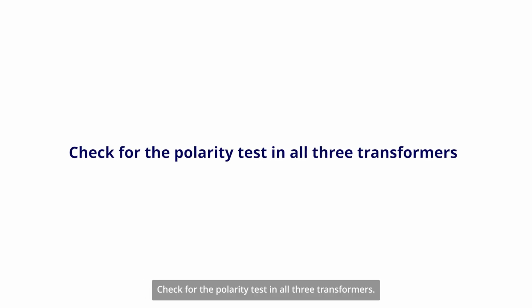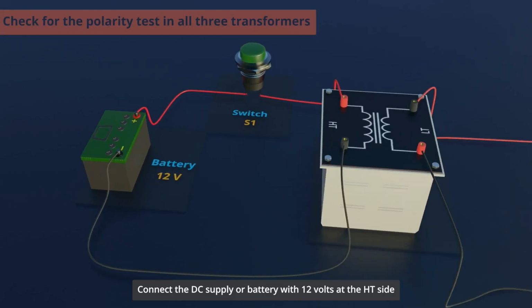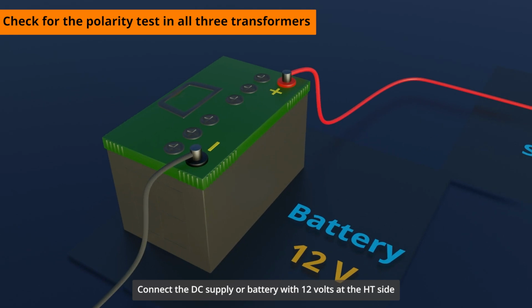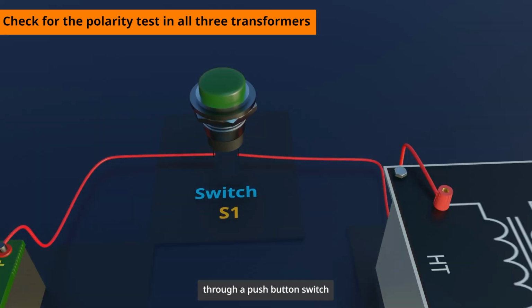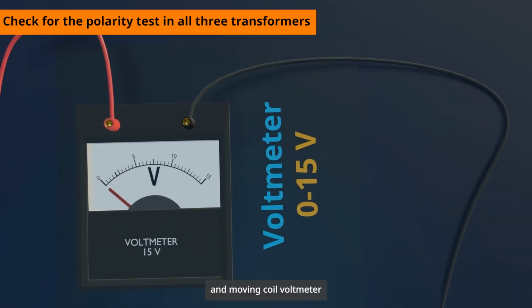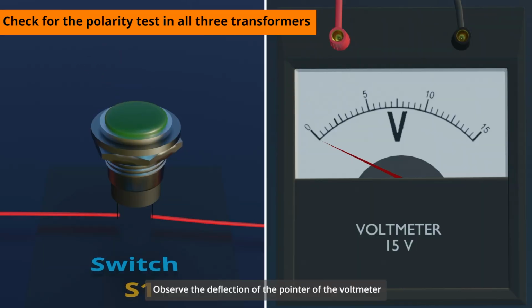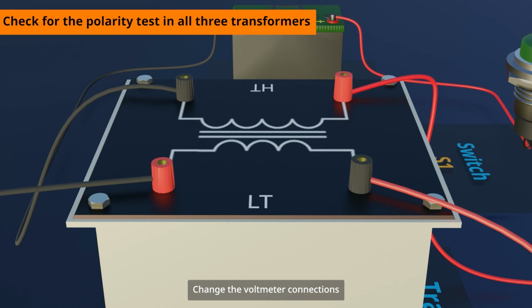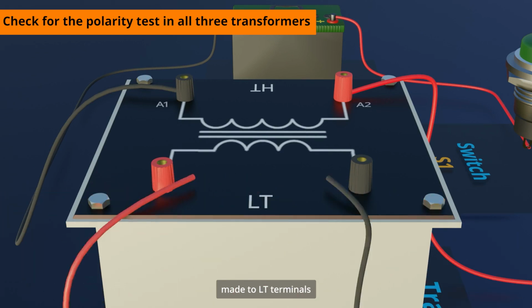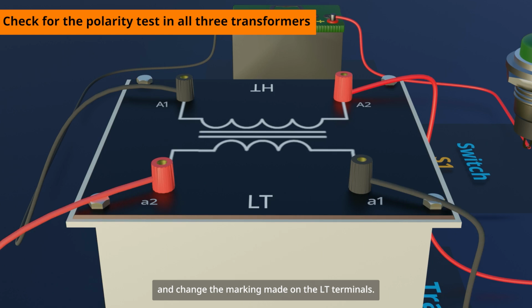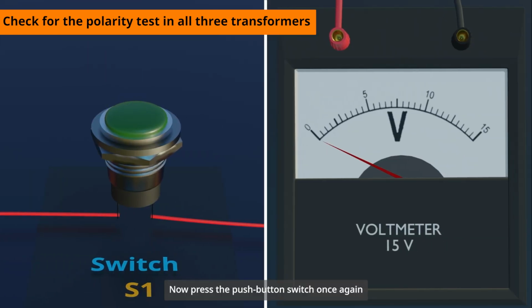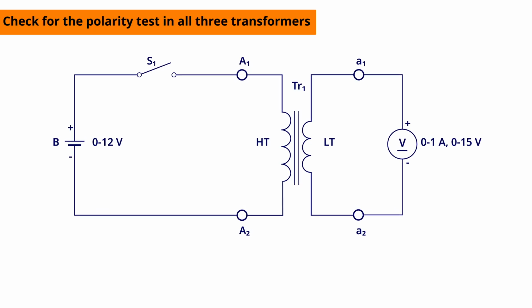Check the polarity test in all three transformers. Connect the DC supply or battery of 12 volts at the HT side through a push-button switch, and a moving coil voltmeter ranging from 0 to 15 volts at the LT side. Press the push-button switch. Observe the deflection of the pointer of the voltmeter at the LT side. If the pointer deflects in the left direction, change the voltmeter connections made to the LT terminals and change the markings made on the LT terminals. Now press the push-button switch once again and observe that the voltmeter deflects in the right direction.